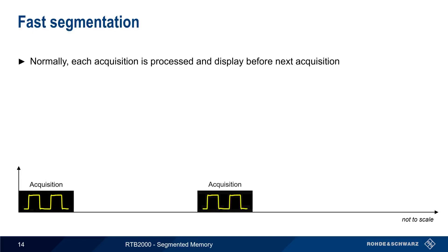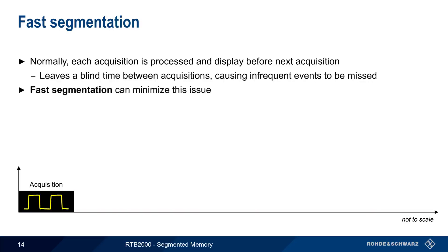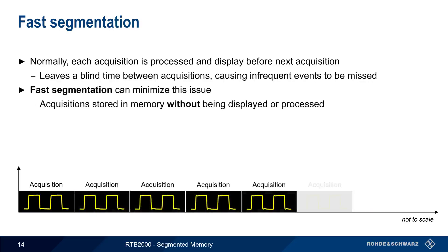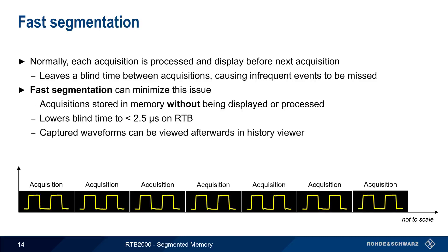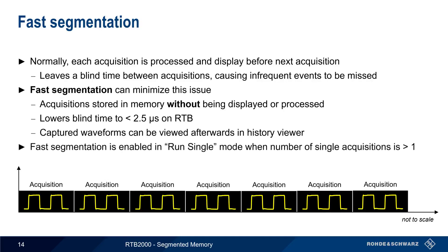An additional feature in History mode is something called Fast Segmentation. When an oscilloscope performs an acquisition, normally each acquisition is processed and displayed before the next acquisition occurs. The time needed to process and display an acquisition creates a blind time during which the scope is not acquiring, and this can lead to infrequent events being missed. When Fast Segmentation is enabled, acquisitions are stored in memory without being displayed or processed. On the RTB, Fast Segmentation lowers blind times to 2.5 microseconds or less. Note that Fast Segmentation must be run in Single Acquisition mode, but with the number of single acquisitions set to greater than 1.